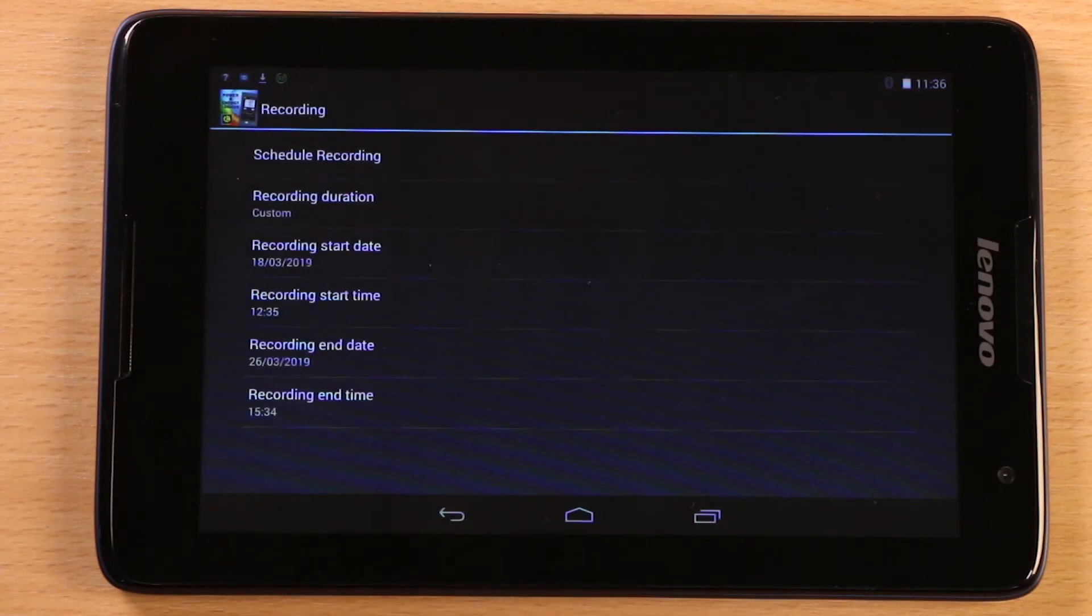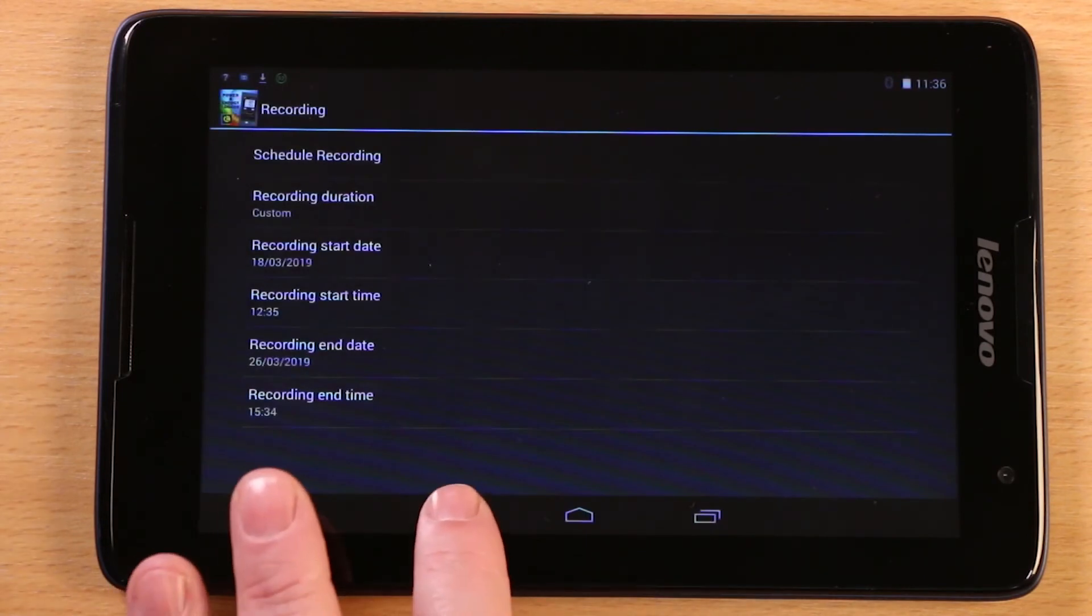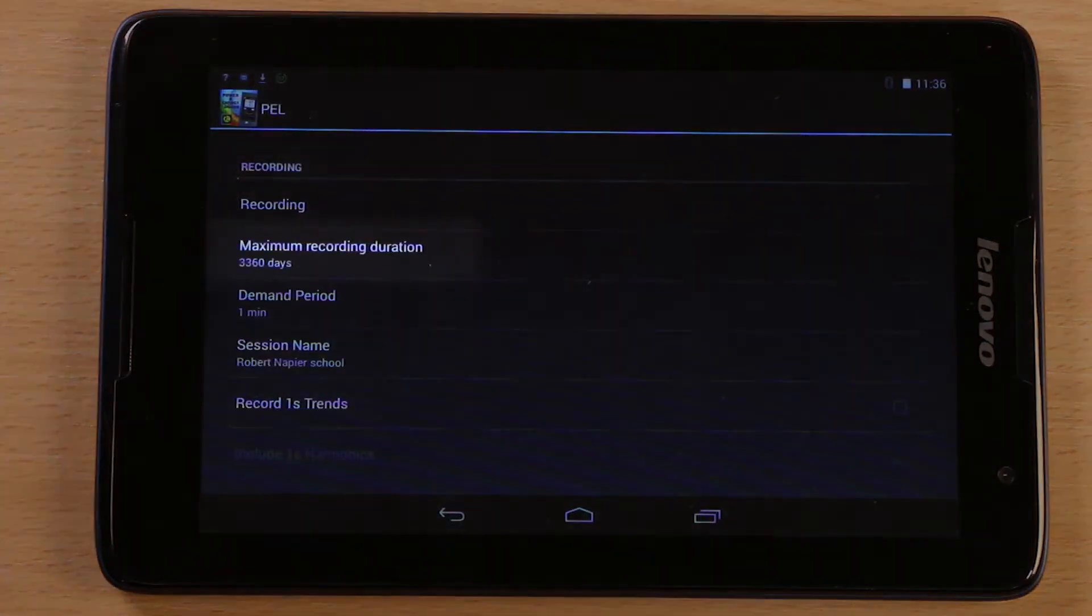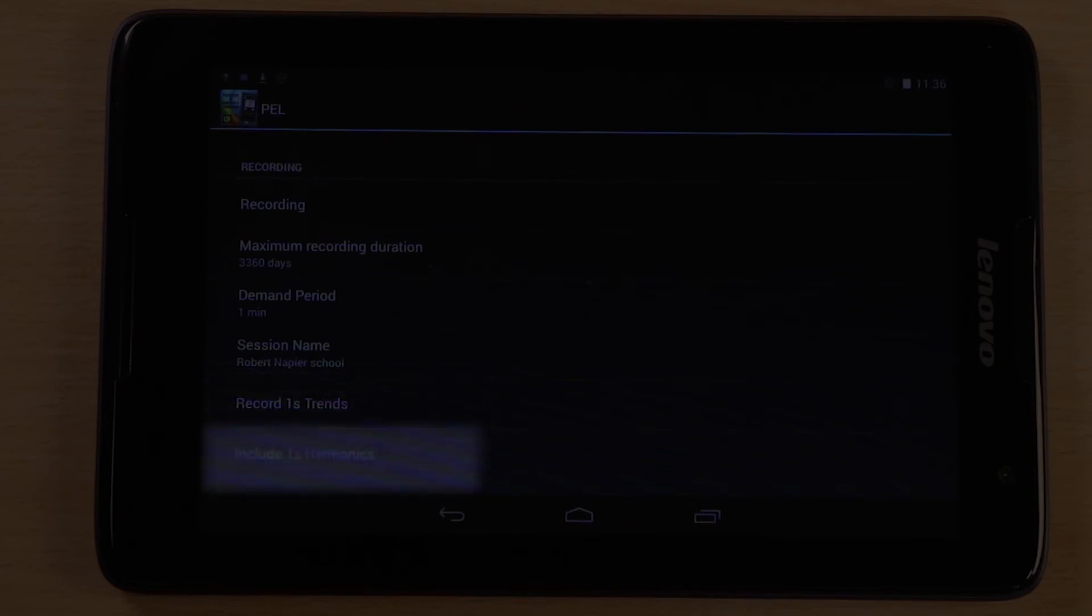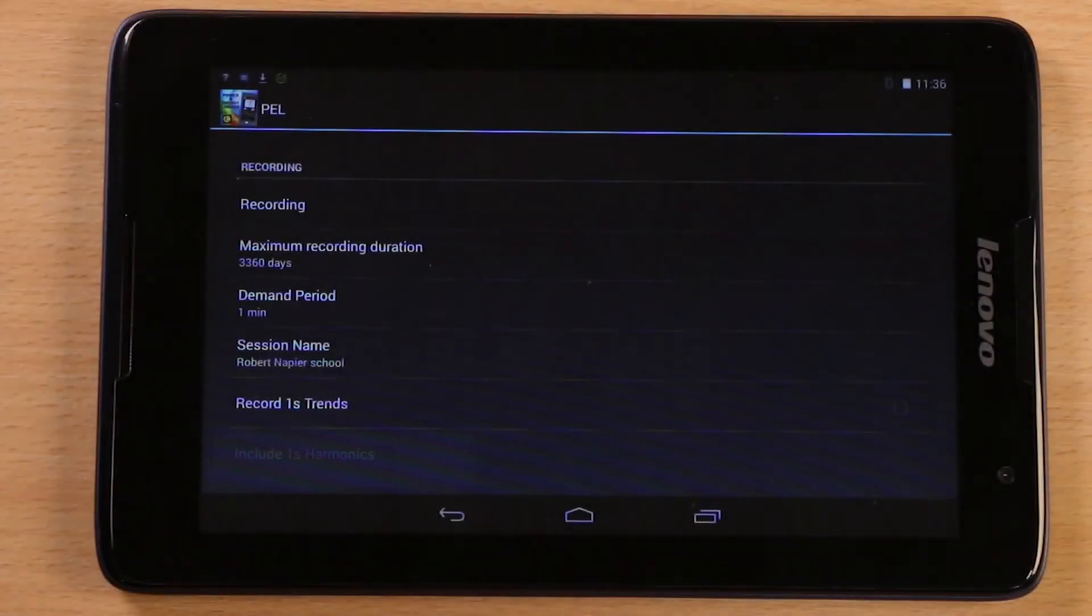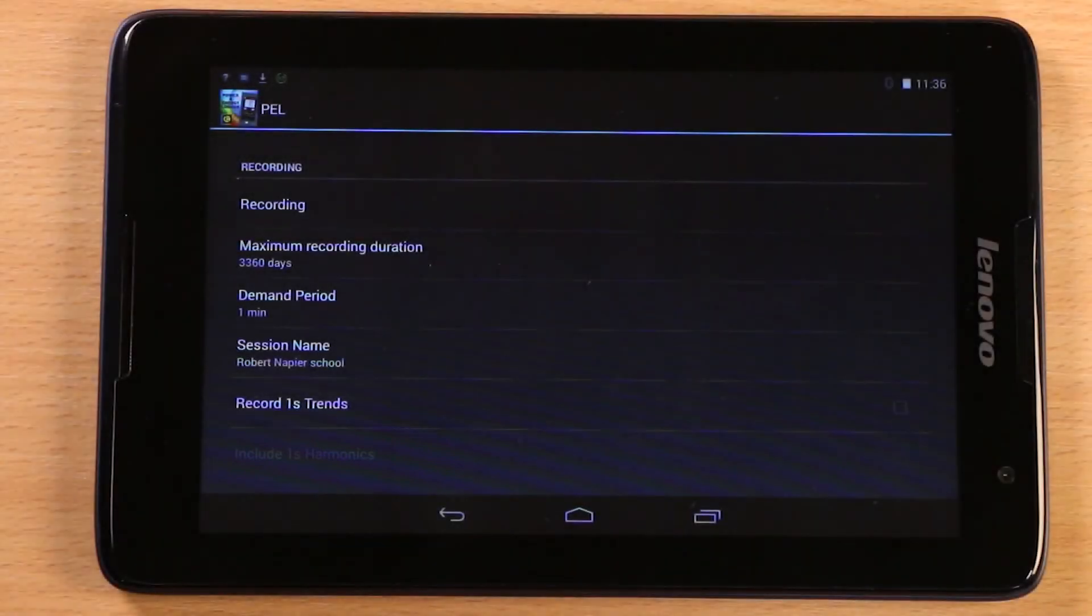Back up one level, you can also see the max recording duration, based on the available space left on the inserted SD card. The demand period or aggregate period, which you can change. You can also see that the option to record one second trends is selected. And for this session, the PEL is not set to record harmonics. Tap on any of these to change their settings.